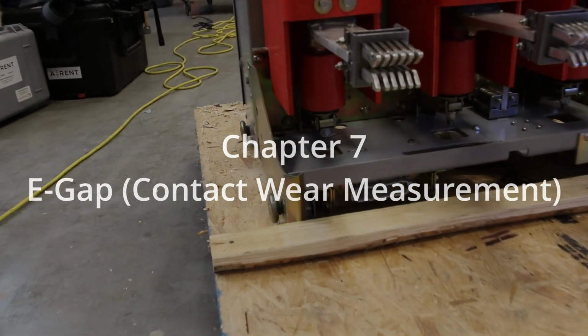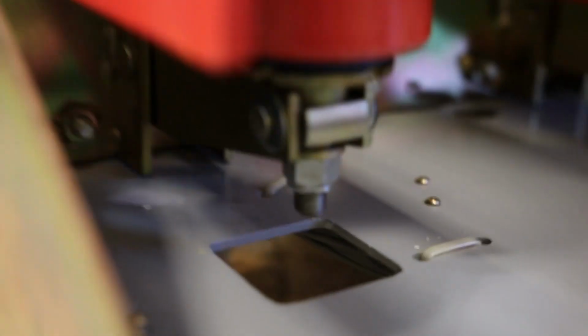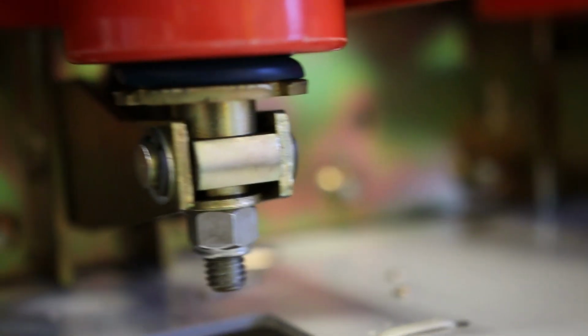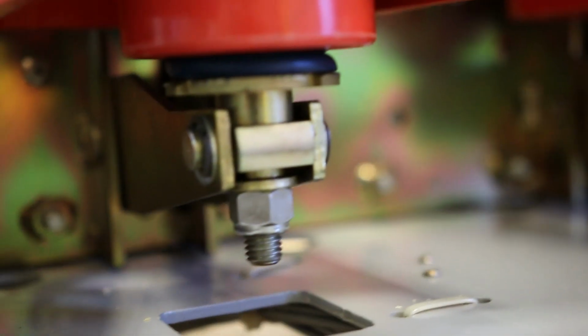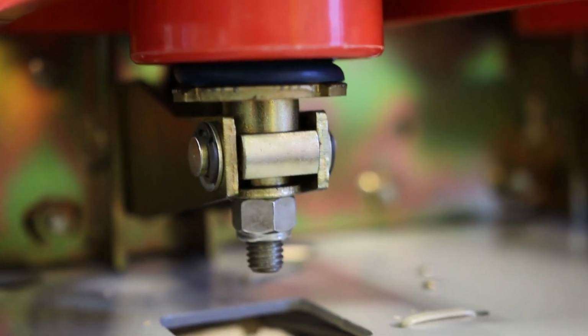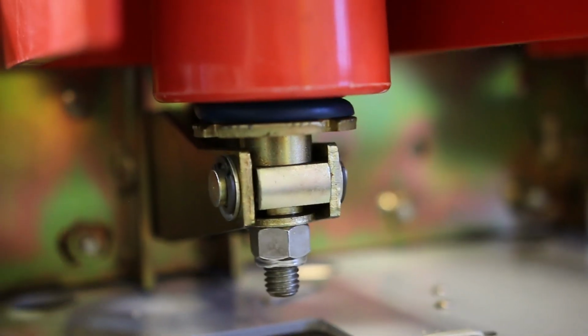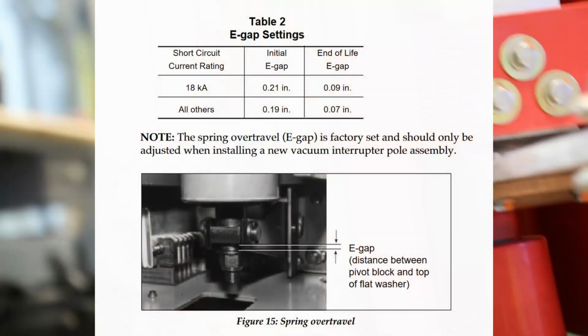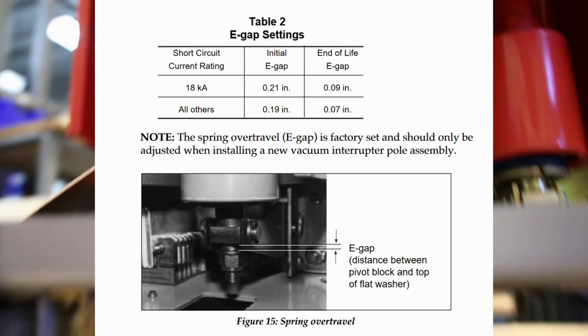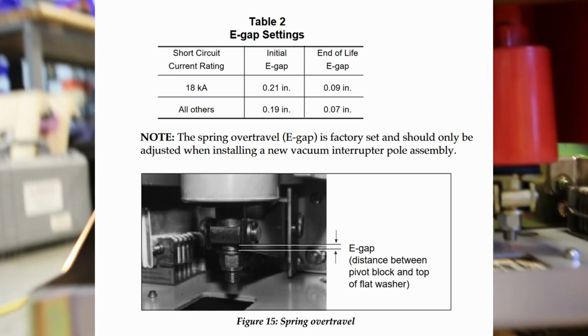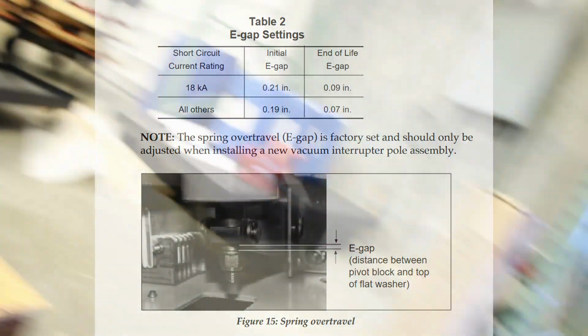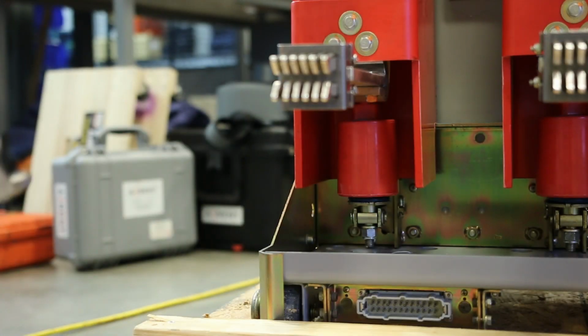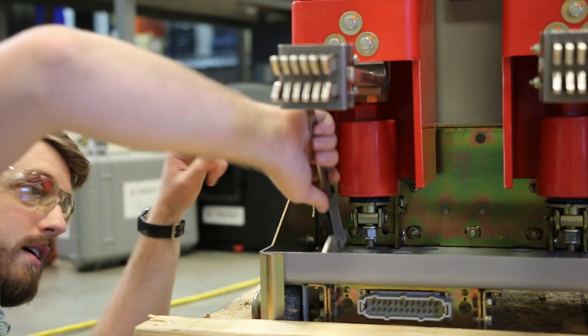All right, one thing that a lot of guys seem to miss, I honestly sometimes forget as well, but with the breaker in the closed position, and this is gonna be different between breaker manufacturers, we need to measure the critical distances. Now on this Square D VR breaker, they tell us that the critical distance with the breaker in the closed position, so we're in the closed position right now, I need to measure this tiny little gap right here, and they call that my E gap. So we're gonna measure that on our calipers, go ahead and zero these out. And we're gonna get in here nice and friendly like.